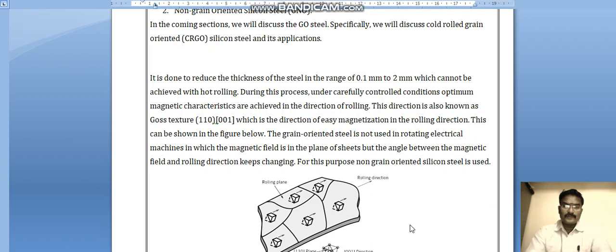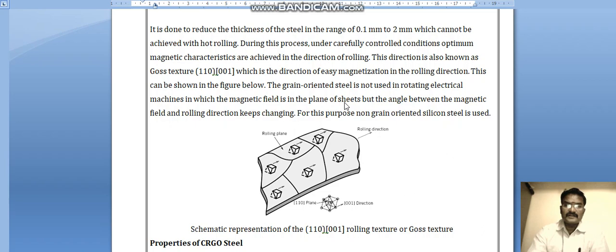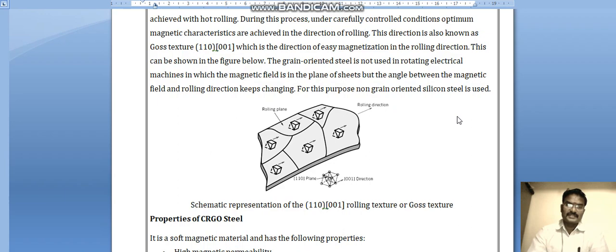Grain oriented steel is not used in rotating electrical machines. It is used for transformers, in which the magnetic field lies in the plane of the sheet. However, in rotating machines the angle between the magnetic field and the rolling direction keeps changing, so for that purpose non-grain oriented silicon steel is used.